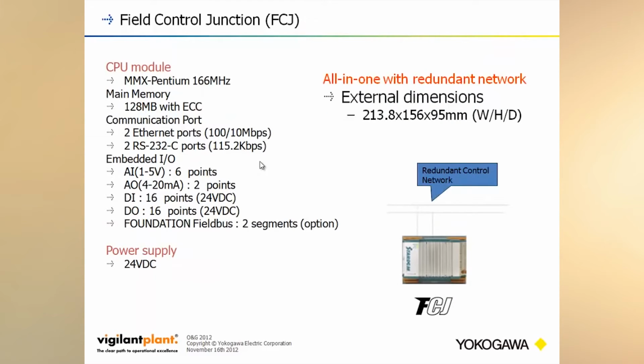The final unit we have is the FCJ, once again with the same Pentium CPUs as the FCN. It continues on with ECC memory, has a couple Ethernet ports and a couple serial ports, so once again you can do redundant serial and redundant Ethernet communications if desired. It's got a good chunk of built-in I/O: 6 analog inputs, a couple analog outputs, 16 digital inputs, 16 digital outputs, and there's an option for a couple foundation field bus segments as well. It's 24-volt power.